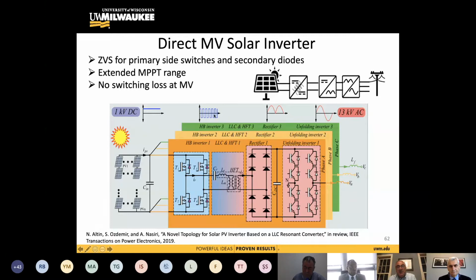Since you make this frequency high—for us, between 30 to 60 kilohertz, and you can vary between that range—doing that we build a rectified DC voltage on this capacitor. From here, we get 6.5 kV IGBTs and run them at line frequency, 60 hertz only, then connect to the grid. Doing this, the switching loss almost goes down to zero because you have 60 hertz switching.